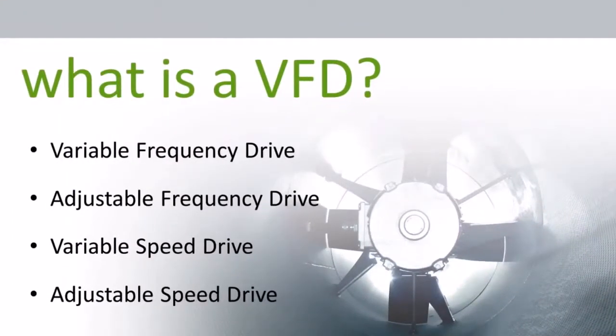Well, some of the different names that are used in the industry are a variable frequency drive, an adjustable frequency drive, a variable speed drive, or an adjustable speed drive. The technology has been around for quite a few years, but has only started to make some headway in HVAC and pumping applications in the last several years. The size and cost of electronics has made VFDs applicable to a wider range of motors and increased the opportunity for savings.